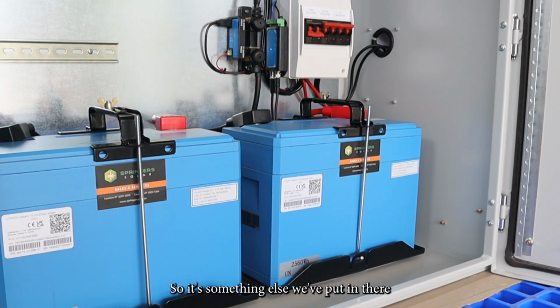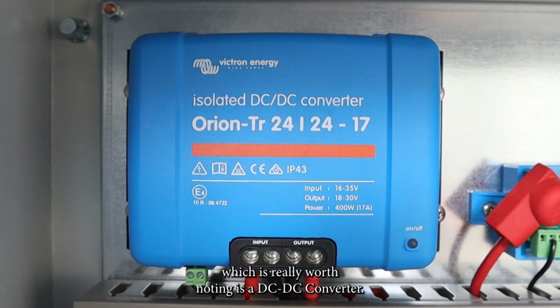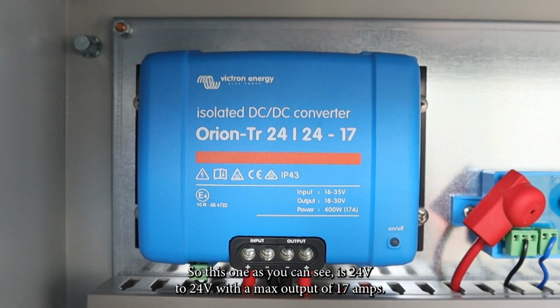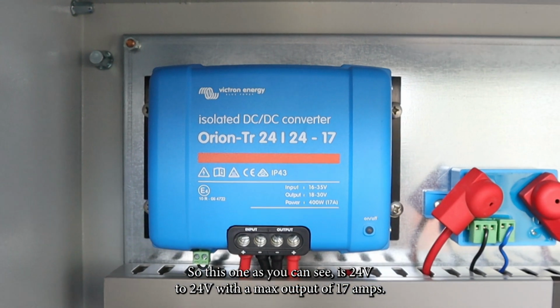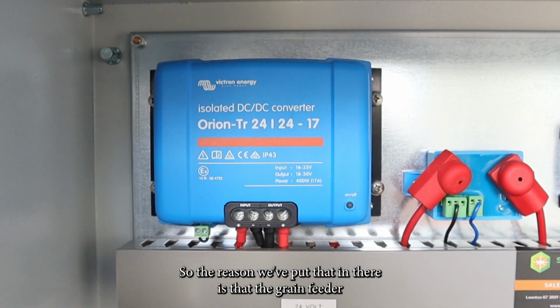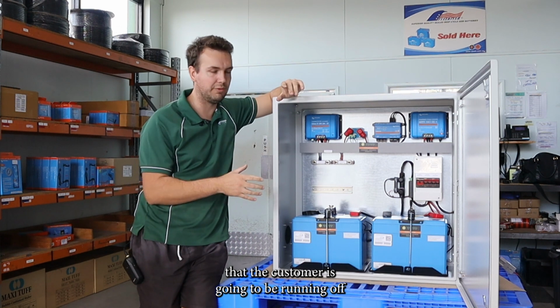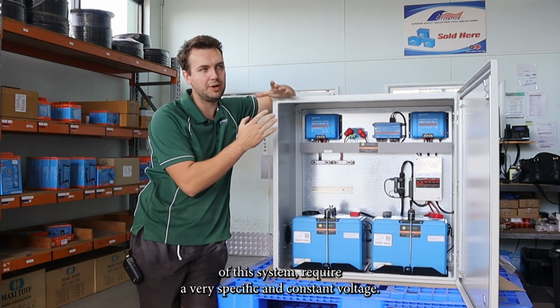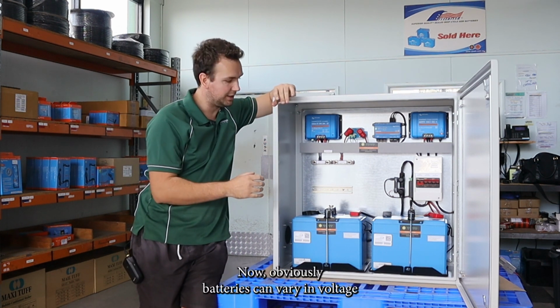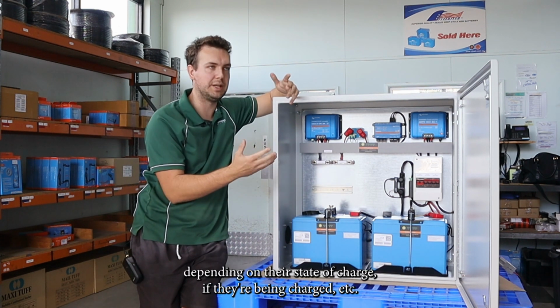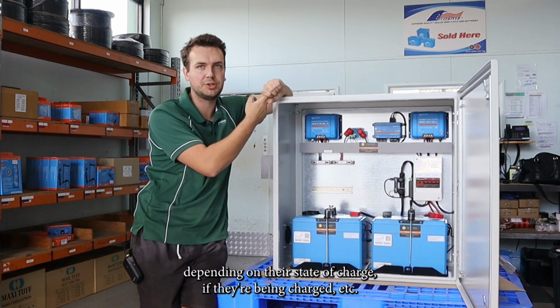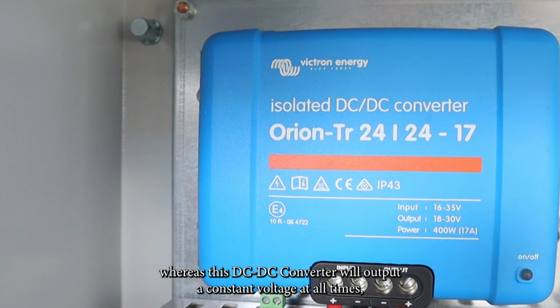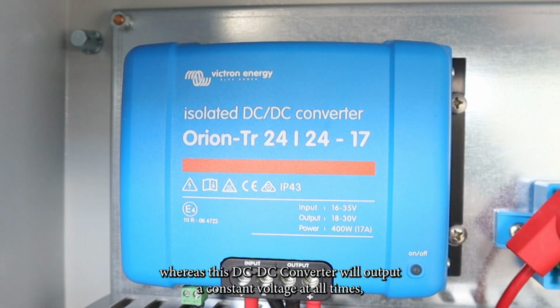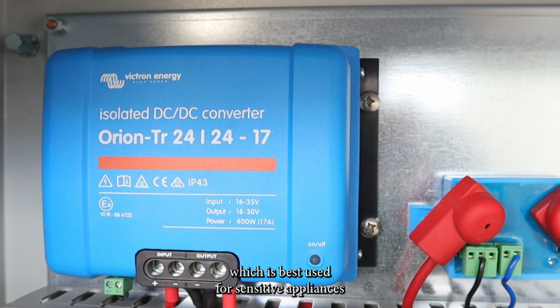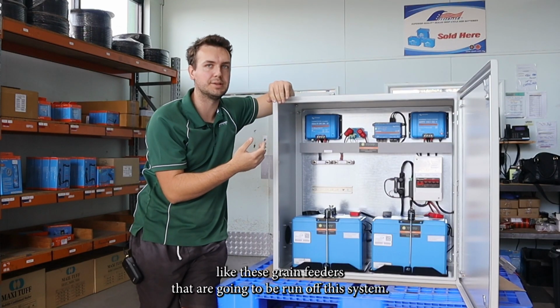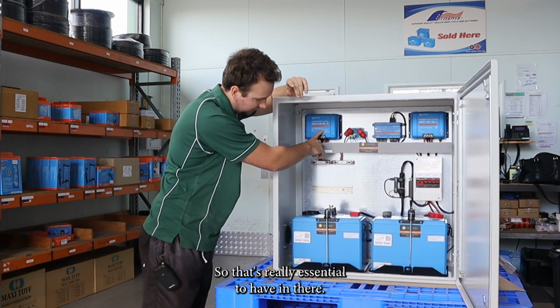Something else worth noting is a DC-DC converter, 24 volts to 24 volts with a max output of 17 amps. We've put that in because the grain feeders running off this system require a very specific and constant voltage. Batteries can vary in voltage depending on their state of charge or whether they're being charged, whereas this DC-DC converter outputs a constant voltage at all times, which is best for sensitive appliances like these grain feeders. That's really essential to have.